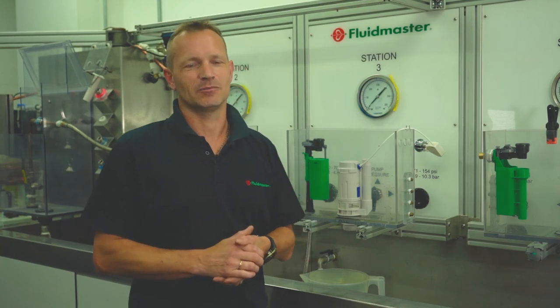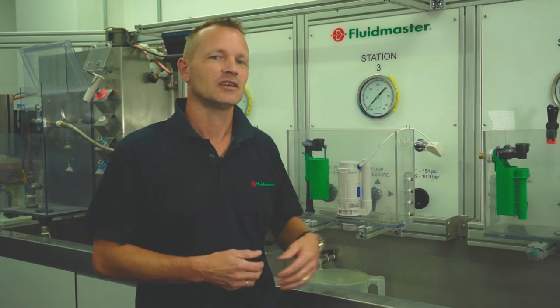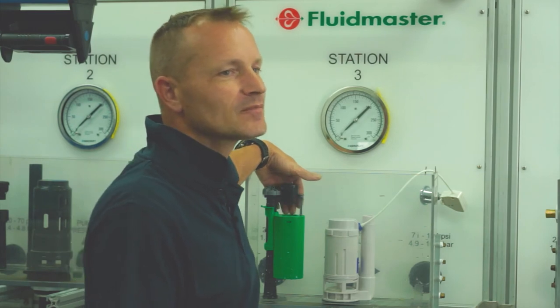We have developed a variety of AirGap 6000 models. The bottom entry delay and non-delay versions are all adjustable in height to accommodate different water levels and different size cisterns, and we've also done the side entry versions, again in delay and non-delay. The 6000 model eliminates backflow dangers — backflow is when water gets drawn from your cistern back into your main water supply and contamination can happen. The air gap from the discharge point of the valve prevents that from happening, which also prevents any need for an additional check valve to be fitted. Finally, we've designed the 6000 so that it's got reliable and great performance at very low pressure, such as gravity fed systems with maybe one or two metre heads, where we need decent flow to fill a cistern quickly.